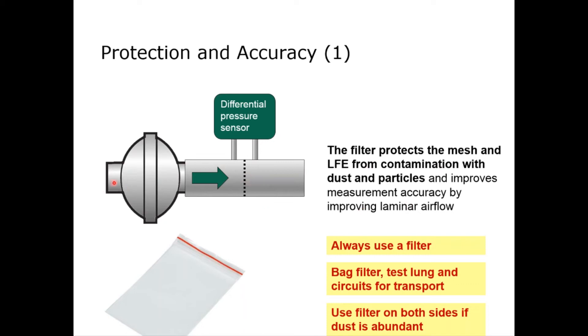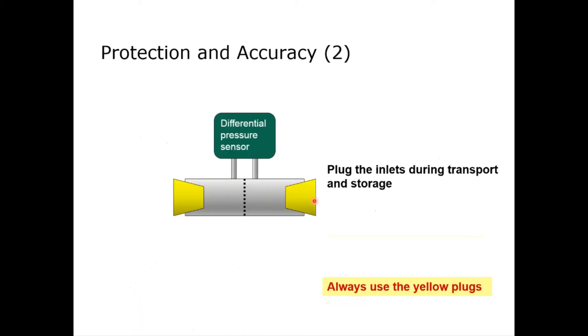If the flow goes both ways, it may in some circumstances be advisable to have a filter on the other side of the PF300 as well, which means on the rear side. This applies especially if you use a test lung on this side which might be full of dust as well. That is something which has to be taken into account.